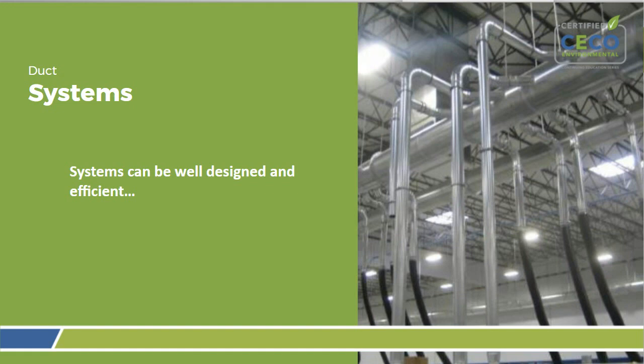Duct systems can be designed well and efficient. What you see here in this photograph, the trunk line is tapering, meaning it's getting bigger as additional lines are entering, so that's good. The elbows you can see are long radius, that's a good design. The T's are entering in at 45 degrees, which is a good thing. The flexos you see below, that's questionable, but this is a woodworking system where the hood is mounted on a track, an automated track where they're machining across a wide plane, so that's needed in this case.